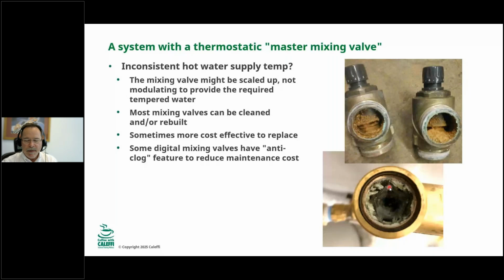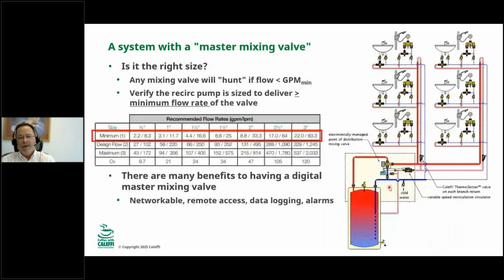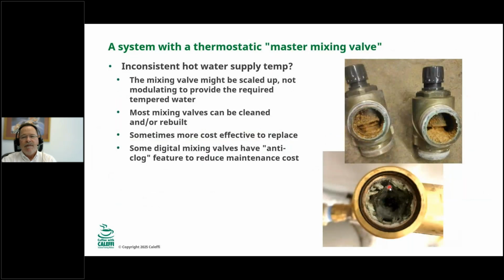All right. Oh, I missed a point here. Some digital mixing valves have a feature called anti-clog or something like that. What the digital mixing valve will do is every night it'll fully open and fully close. And what that feature is for is to kind of clean off any buildup or scale that's on the seat of the valve. And the Caleffi valve does that, and that makes it a pretty good feature. If someone has really hard water and they know that scaling is a problem and they have to rebuild their master mixing valves all the time, that can really help with maintenance costs.